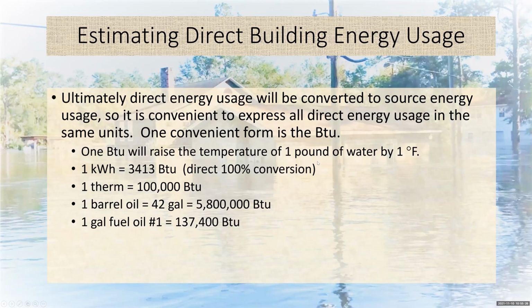Need a few more numbers. And again, mechanical engineers and electrical engineers and everybody loves numbers. I can't imagine anybody not realizing and being thrilled to know that a kilowatt hour is equivalent to 3,413 BTUs if it's converted directly into BTUs, which is pretty much the case in an electric water heater. You got that heating element inside the water heater. There's not much else anywhere else for that energy to go other than heating the water.